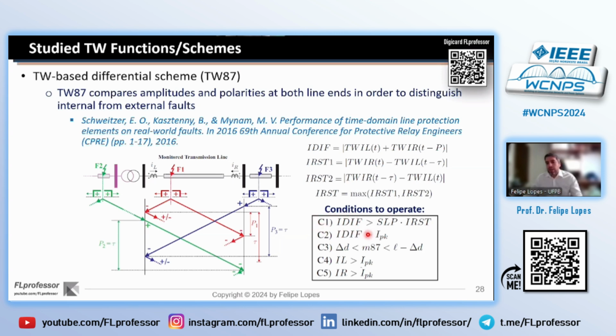in order to apply operating conditions, like the classical ones, which compare differential quantities with a slope multiplying a restraining current. They can compare the differential current with a pickup value. They can verify whether the traveling waves measured at both line terminals exceed a pickup value, and also a security layer here, which considers the fault location function just to make sure that the fault is within the line.